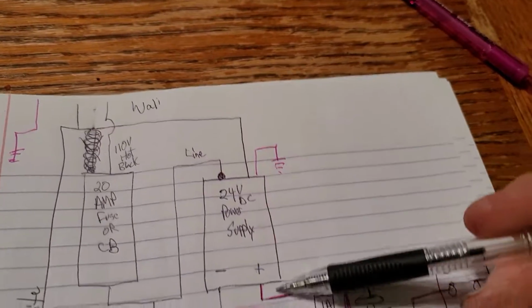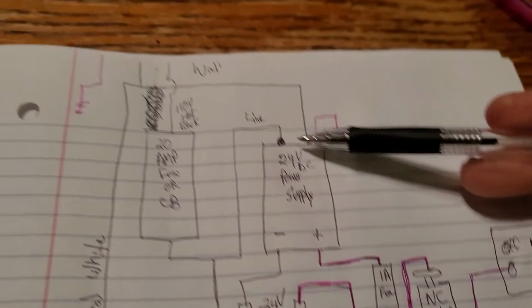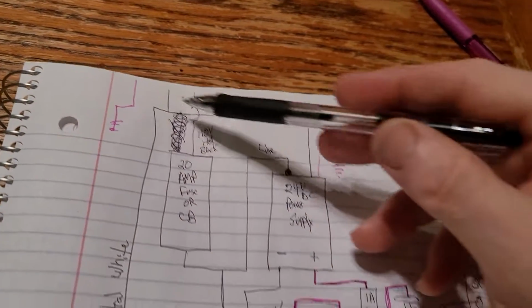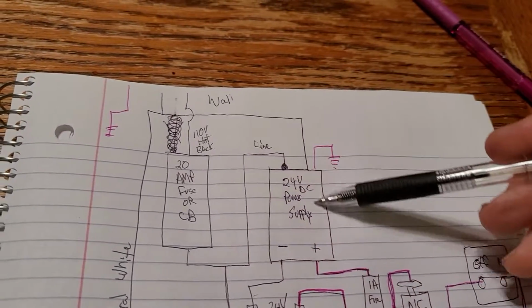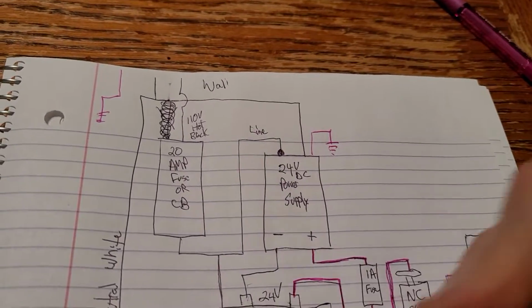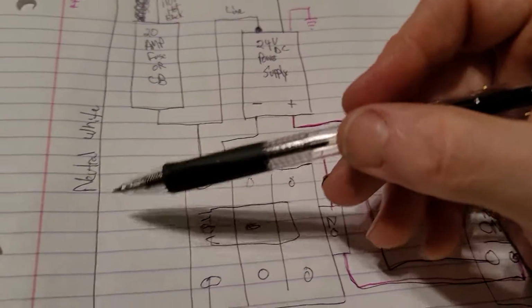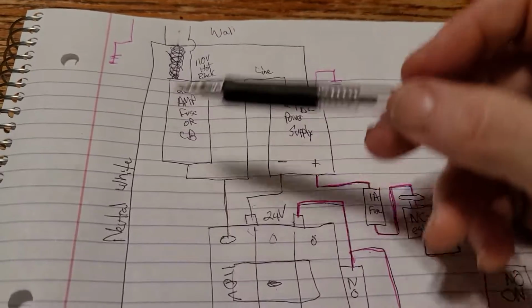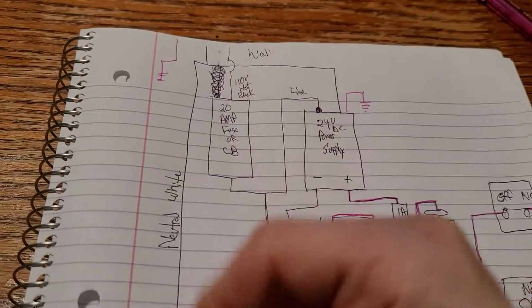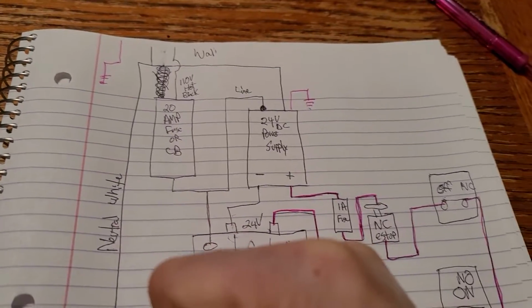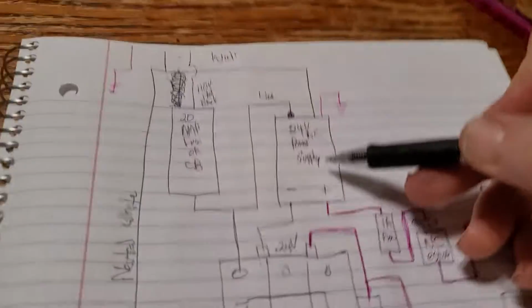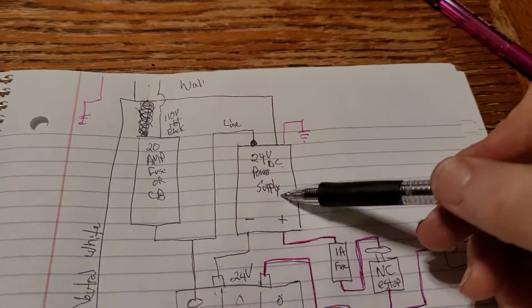This 24 volt power supply, once we've supplied power into it from the top, and we've also got the neutral running here, and then neutral going in. You do not switch neutral. Never switch neutral in anything you design for 110 volts. That's why that line's just going all the way down to the devices here. It doesn't go anywhere. But you have to supply voltage to this power supply.